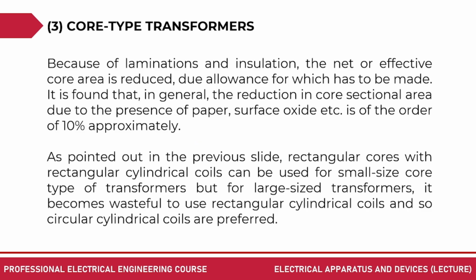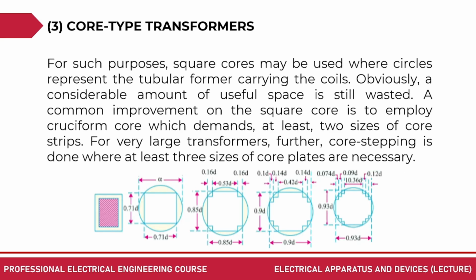Next, because of the laminations and insulation, the net or effective core area is reduced. Due allowance for which has to be made. It is found that in general, the reduction in core sectional area, due to the presence of papers, surface oxide, etc., is of the order of 10% approximately. As pointed out in the previous slide, rectangular cores with rectangular cylindrical coils can be used for small size core type transformers, but for large size transformers, it becomes wasteful to use rectangular cylindrical coils, and so circular cylindrical coils are preferred. For such purposes, square cores may be used where circles represent the tubular former carrying the coils. Obviously, a considerable amount of useful space is still wasted.